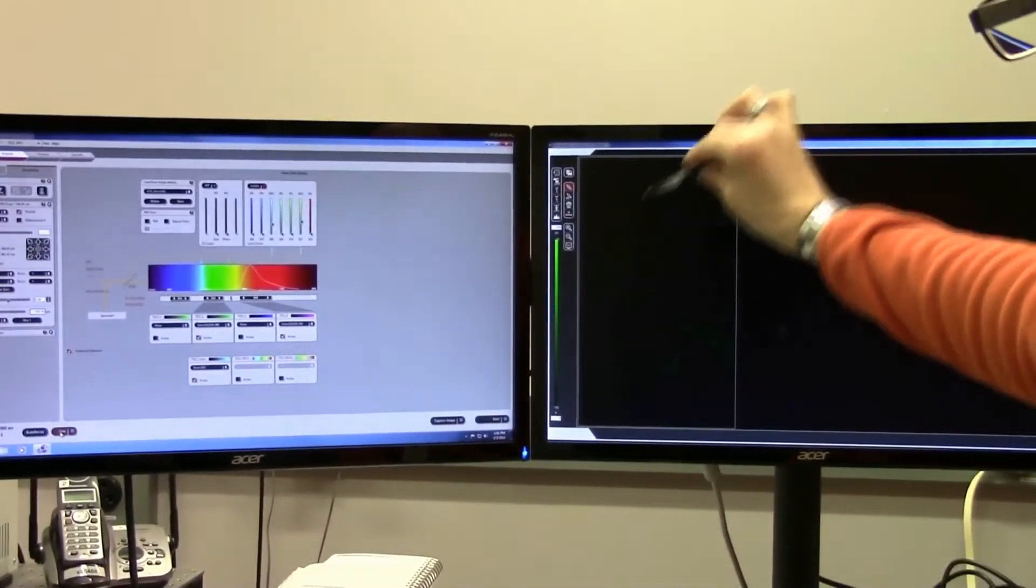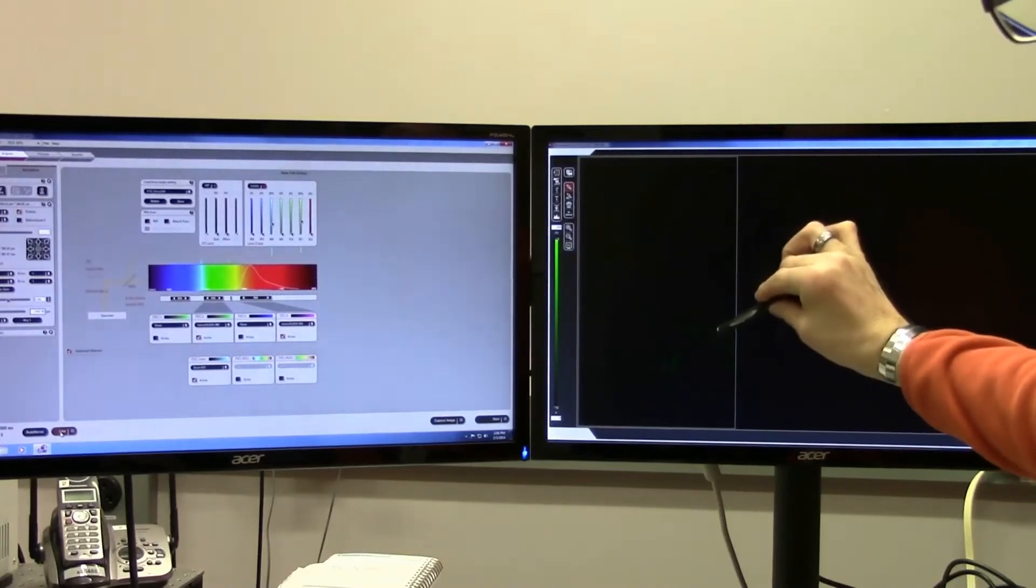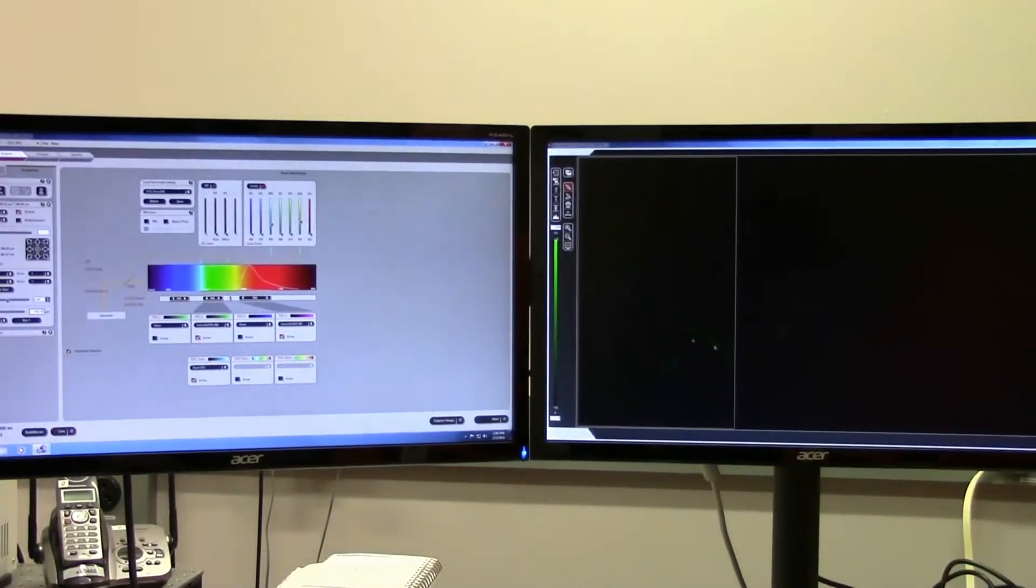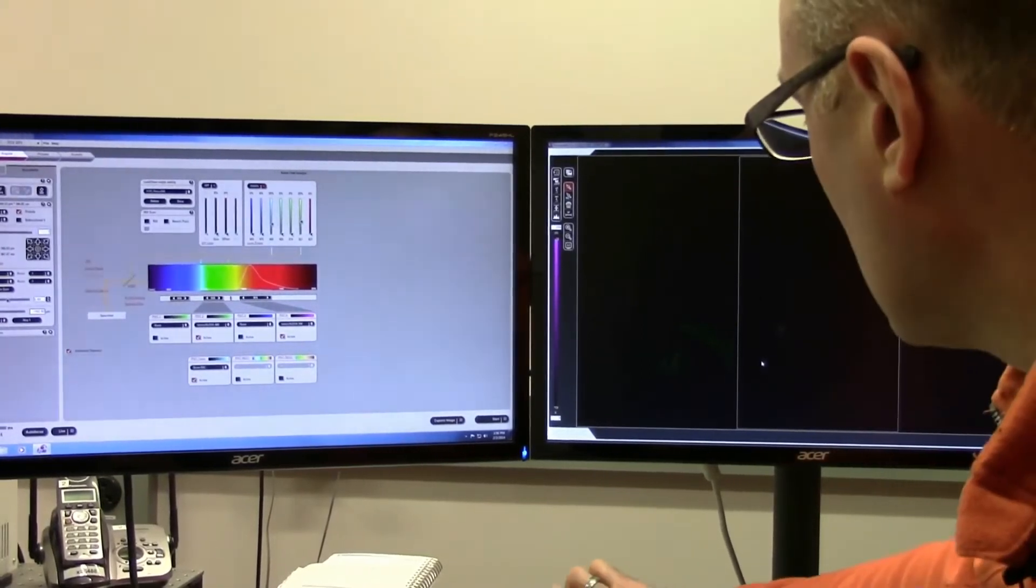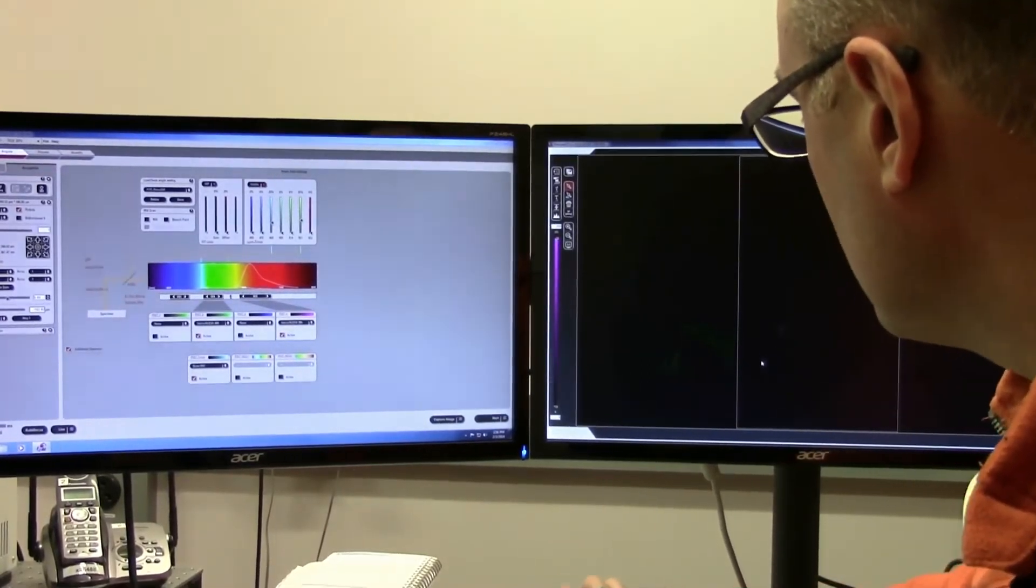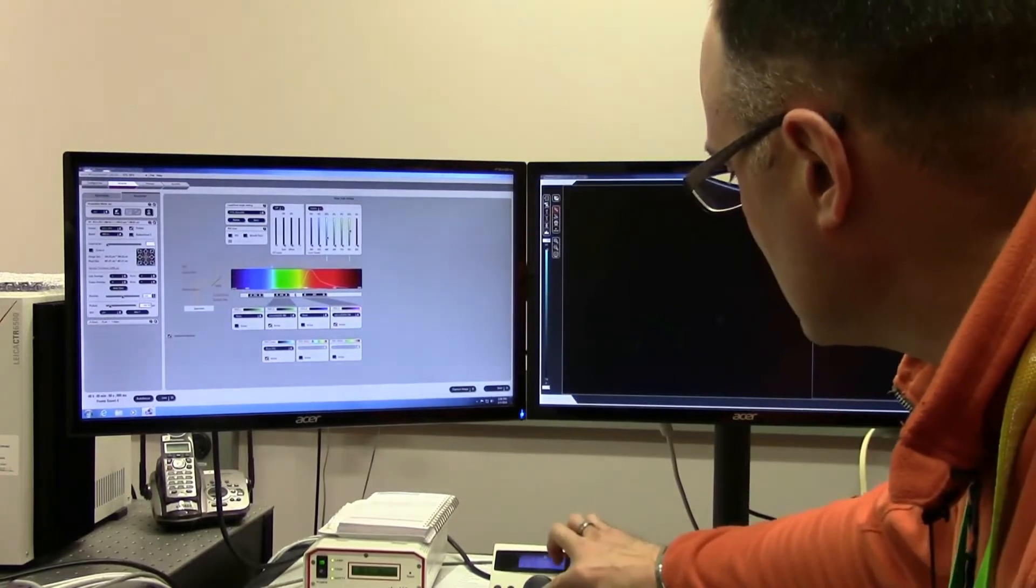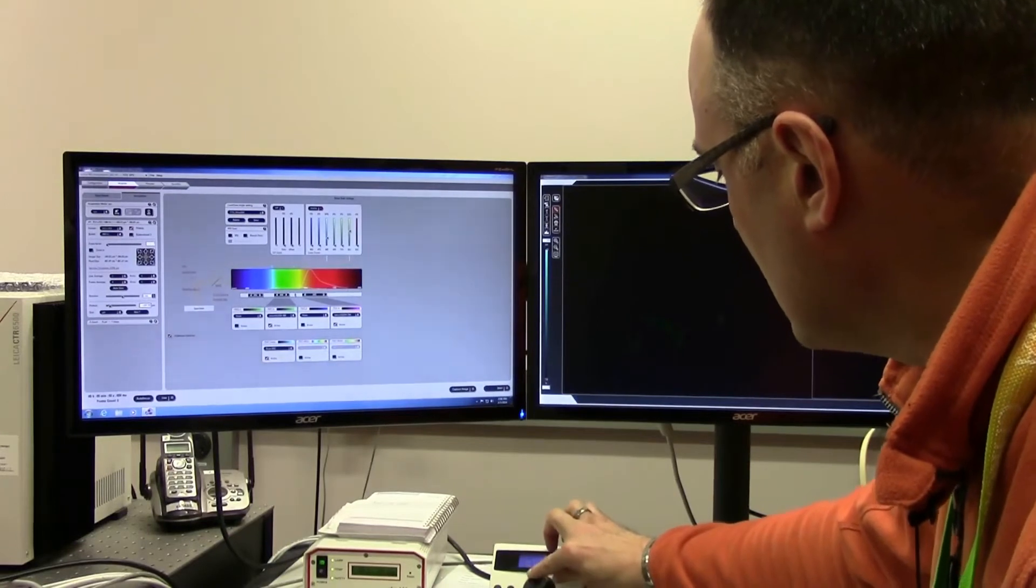Our preliminary data shows that in our green channel, we do have signal. If we switch over to the red channel, it looks like our gain is not high enough, so we will turn up the gain, and we may need to turn up the laser light. In the third channel, which is our DIC channel, the gain has been set to zero, so we'll turn the gain up.